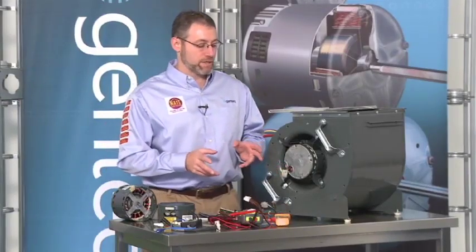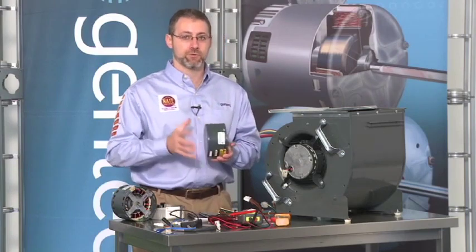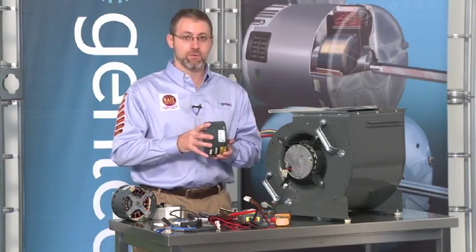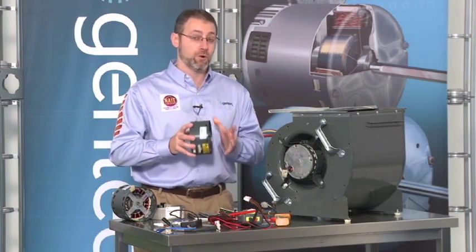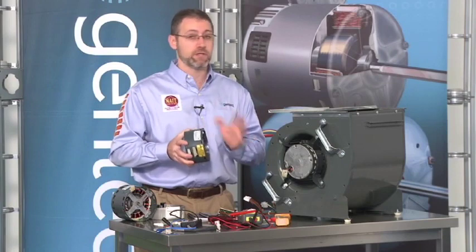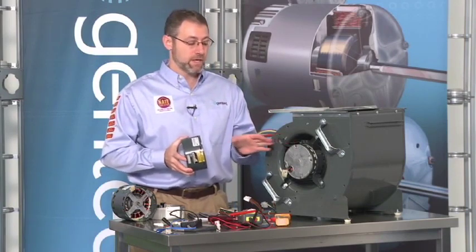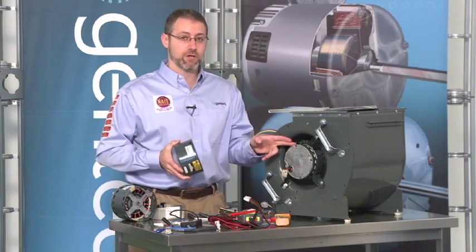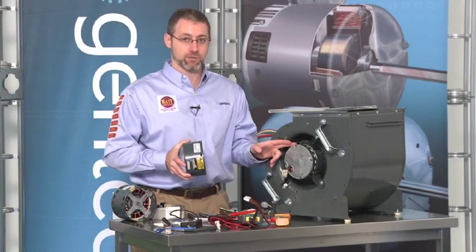So we've diagnosed with our ohm meter that the motor is good. That means that all I have to do is replace the motor control, which you can get motor control separate from the manufacturer only on variable speed motors. That's the only ECM motor you can replace the control separate from the motor. If with our ohm meter we diagnosed that the motor was also failed, then we would have to replace the motor and the control.